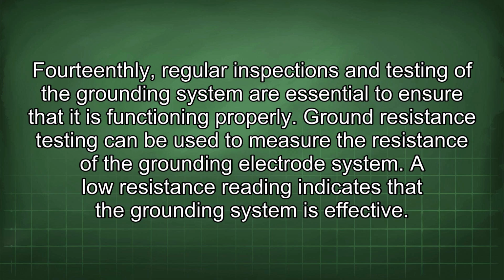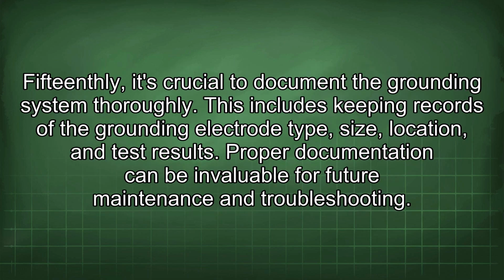14thly, regular inspections and testing of the grounding system are essential to ensure that it is functioning properly. Ground resistance testing can be used to measure the resistance of the grounding electrode system. A low resistance reading indicates that the grounding system is effective. 15thly, it's crucial to document the grounding system thoroughly. This includes keeping records of the grounding electrode type, size, location, and test results. Proper documentation can be invaluable for future maintenance and troubleshooting.